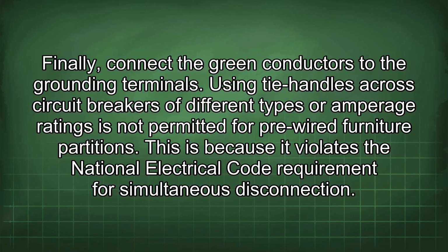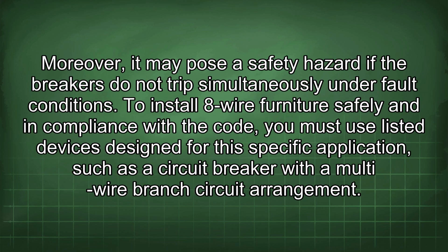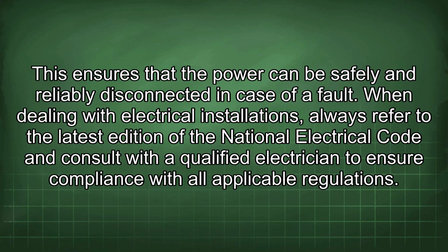Using tie handles across circuit breakers of different types or amperage ratings is not permitted for pre-wired furniture partitions. This is because it violates the National Electrical Code requirement for simultaneous disconnection. Moreover, it may pose a safety hazard if the breakers do not trip simultaneously under fault conditions. To install 8-wire furniture safely and in compliance with the code, you must use listed devices designed for this specific application, such as a circuit breaker with a multi-wire branch circuit arrangement. This ensures that the power can be safely and reliably disconnected in case of a fault.